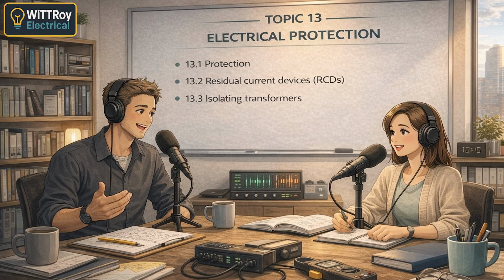Okay. Now, let's look at Regulation 24. This comes up a lot. That's about when an RCD is electrically unsafe, right? Exactly. Let's focus on a 30 milliamp RCD first. Okay. At rated current, 30 milliamps, how quickly must it trip? Is it 40 milliseconds? That's at 5 times rated current. Oh, right. At rated current, it must trip within 300 milliseconds. Okay, 300 milliseconds at 30 milliamps.